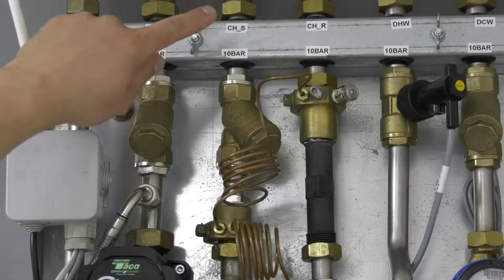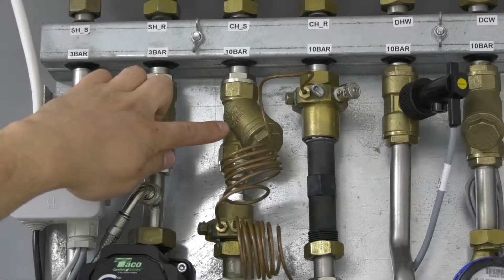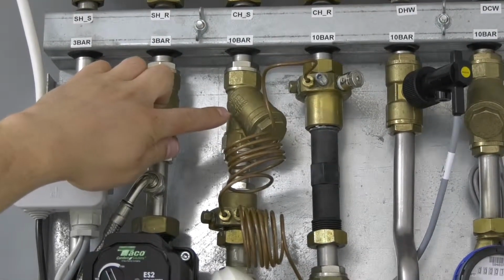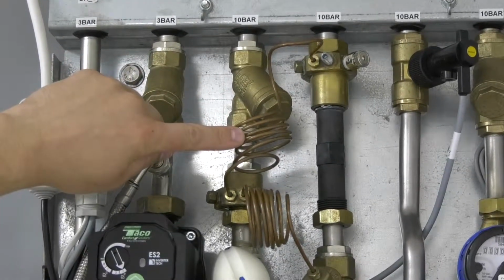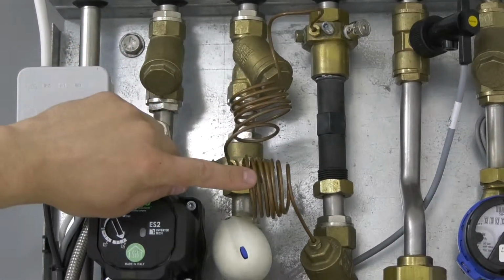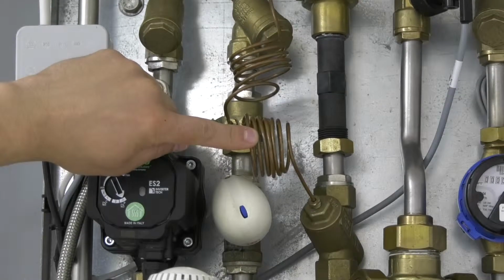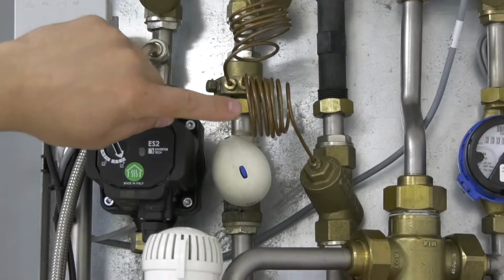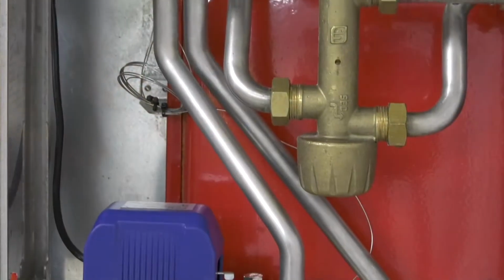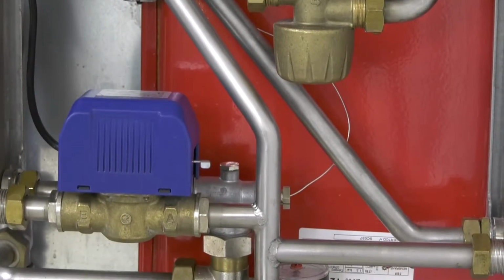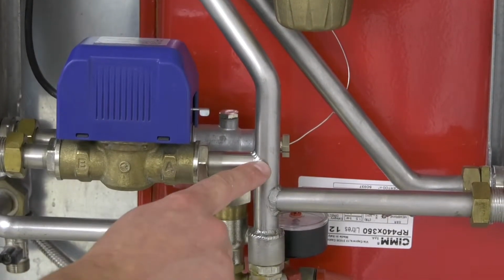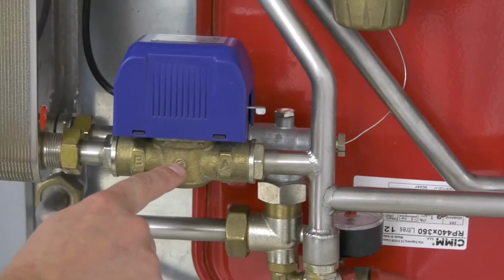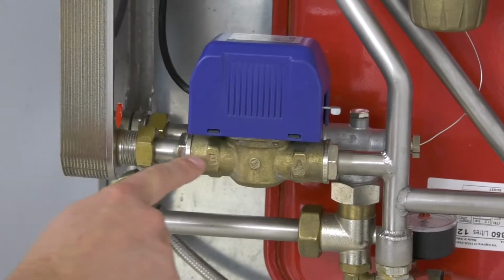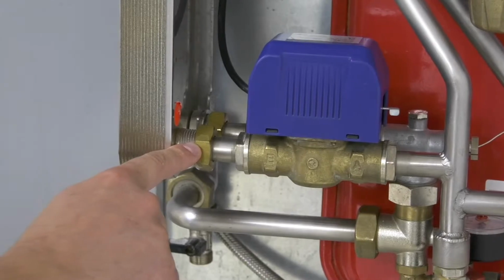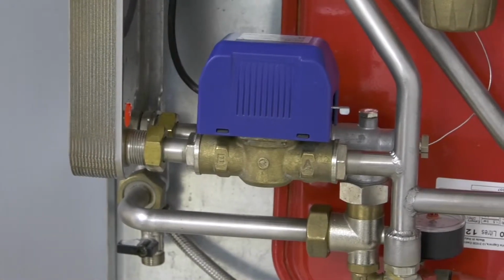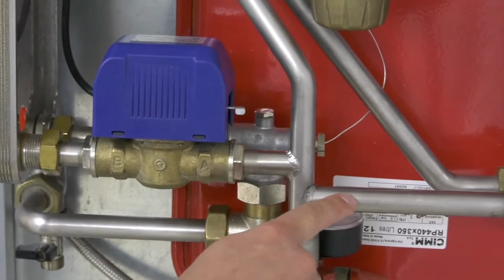Returning to the top of the unit and following the primary flow inlet down, there is the primary strainer, trickle bypass, the connection for the differential pressure control valve, the occupancy solenoid, and following the pipe down you'll then come to the tee-off to the heating zone valve, into the plate heat exchanger heating primary inlet, and the other way tees off to the hot water primary inlet.